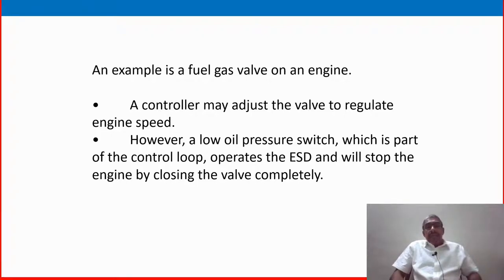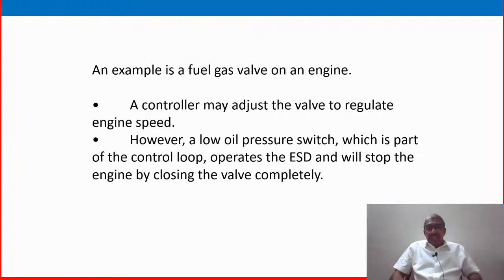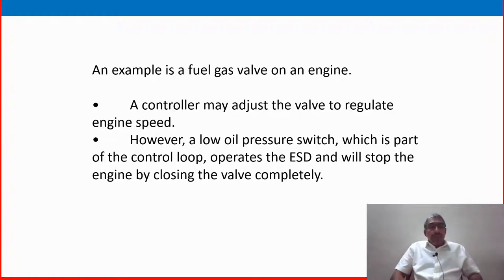Let's look at some simple examples to understand equipment protection. An example is a fuel gas valve on an engine. A controller may adjust the valve to regulate the engine speed and fuel injection. However, a low oil pressure switch, which is part of the control loop, operates the ESD and will stop the engine by closing the valve completely.